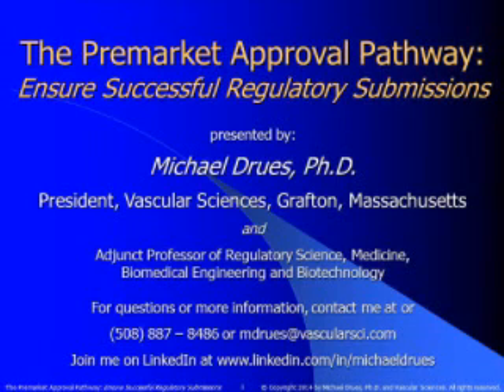So the de novo pathway is a form of down classification. It allows us to argue that the risk is not significant enough to justify doing a PMA, and we can lower it down to Class 2, or maybe even Class 1. That's the essence of the de novo, and the crux to a successful de novo submission is your risk mitigation strategy. I don't care if you've dotted all of your I's and crossed all your T's, if you do not have a very strong risk mitigation strategy, you will not be successful.